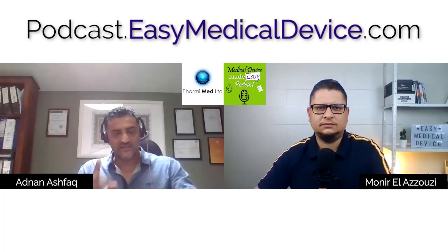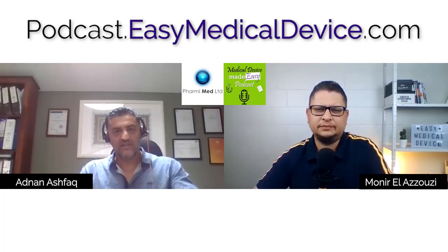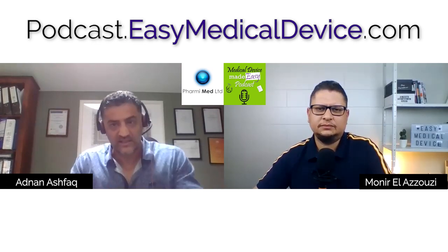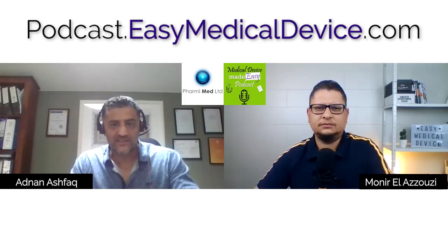This is the main issue: what the notified bodies and the competent authorities are trying to pin down with legal manufacturers is to make sure that compliance and safety standards are being met. So this is actually all about safety. That is the first thing I want to mention. So 62304 is the fundamental standard, but alongside that is 82304, which is another standard, for health software. But the interesting thing is, if you look at 82304, it actually points you back towards 62304. So this is really the main standard that we should be talking about today.